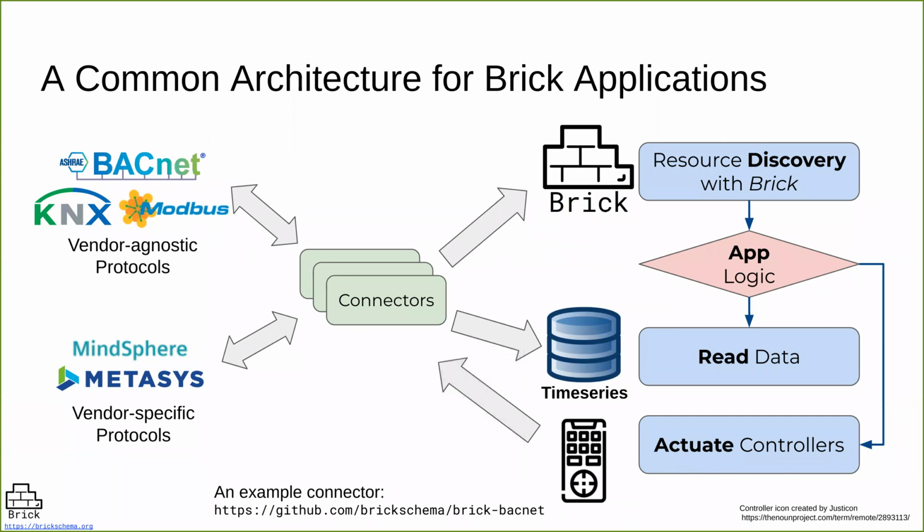Those connectors relay the data from the data sources to databases that our applications can access, including Brick databases for metadata and time series databases for telemetry, and possibly some supervisory control interface. There are many implementations for both metadata and time series databases, but to just name a few: RDF stores, HodDB by Gabe, RDFLib, or AWS Neptune, and so on. Or you can even use Brick with other types of databases too, like your favorite document database or SQL databases, and so on. And there are just too many options for time series databases, like TimescaleDB or InfluxDB.